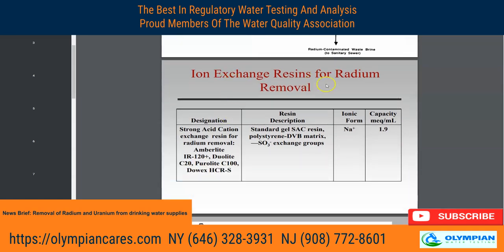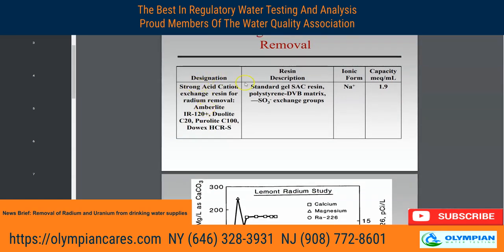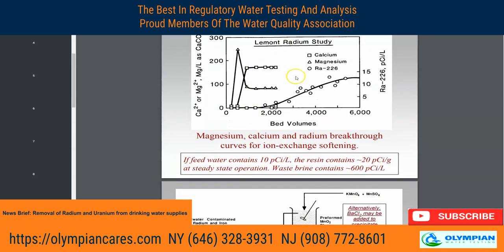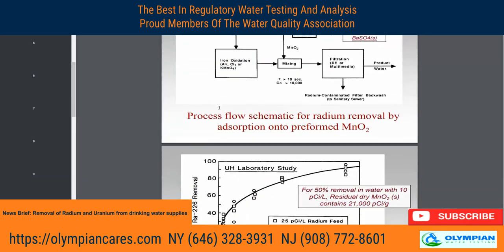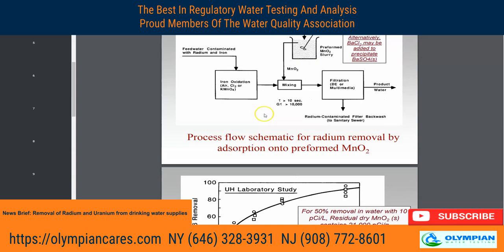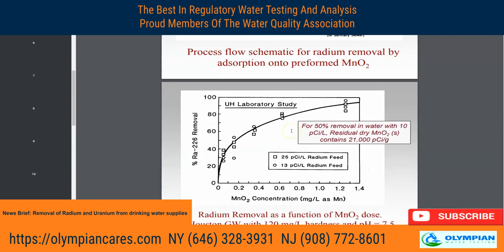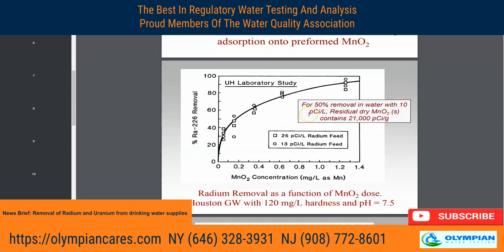We also have the ion exchange resins for radium removal right here, with designation with strong acid cation resin for radium removal, Amberlite, Duolite, and we have the resin description here as well, with the Lemont Radium Study. We can also see the process for sorptive radium removal by adsorption performed with HMO. And for 50% removal in water with 10 picocuries per liter, residual dry MnO2 contains 21,000 picocuries right here.